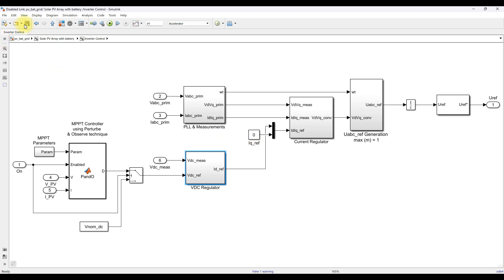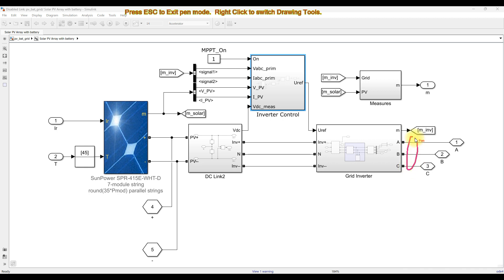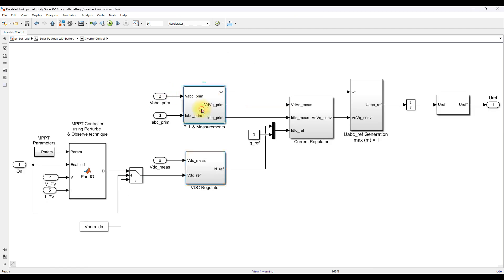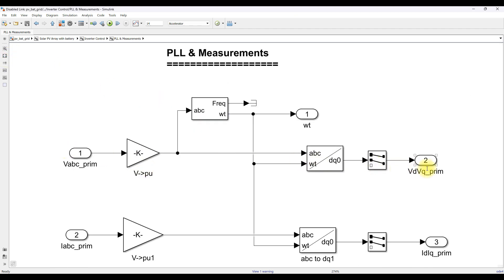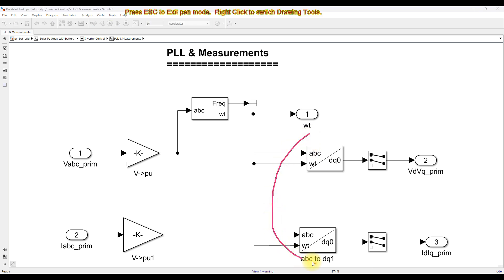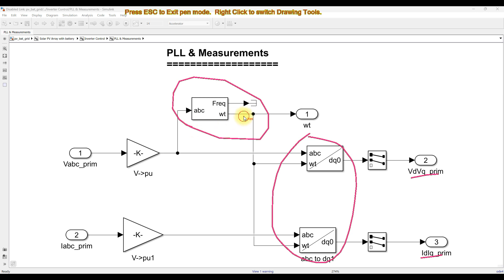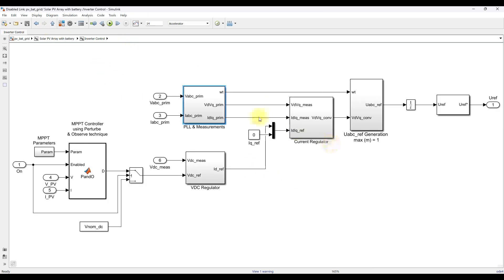At the inverter connection point to the point of common coupling, we measure the voltage and current. These are in ABC form and need to be converted to DQ form using ABC to DQ0 power transformation. After the transformation we obtain vd, vq, id, and iq. A PLL is used to generate the omega-t angle required for this transformation block.